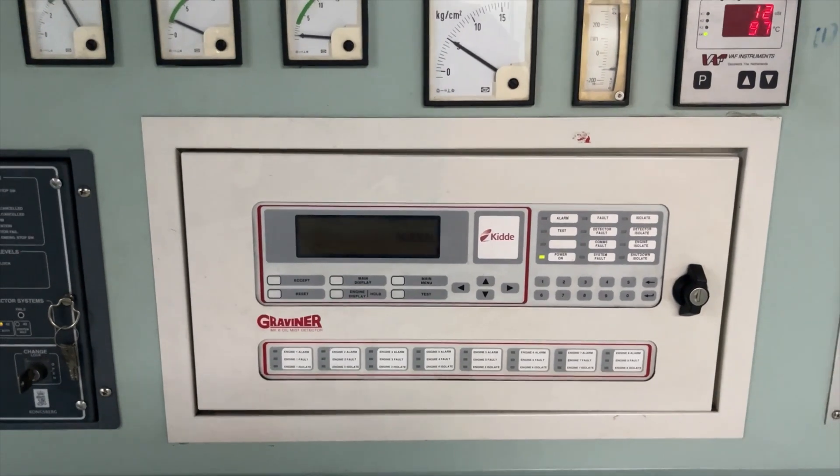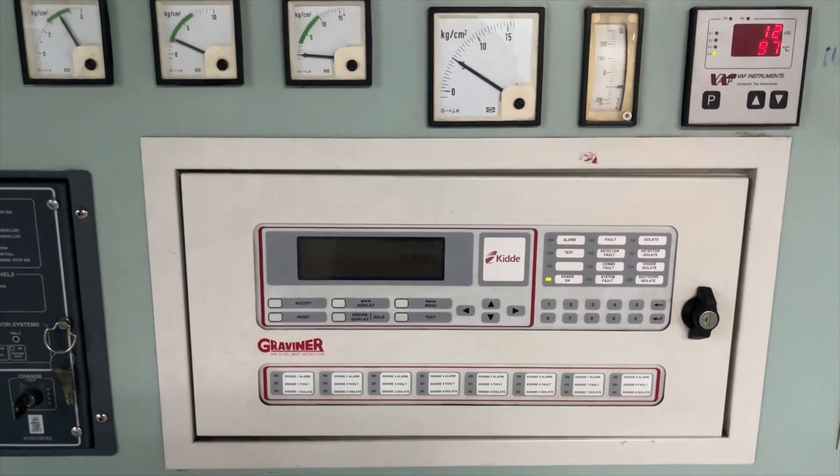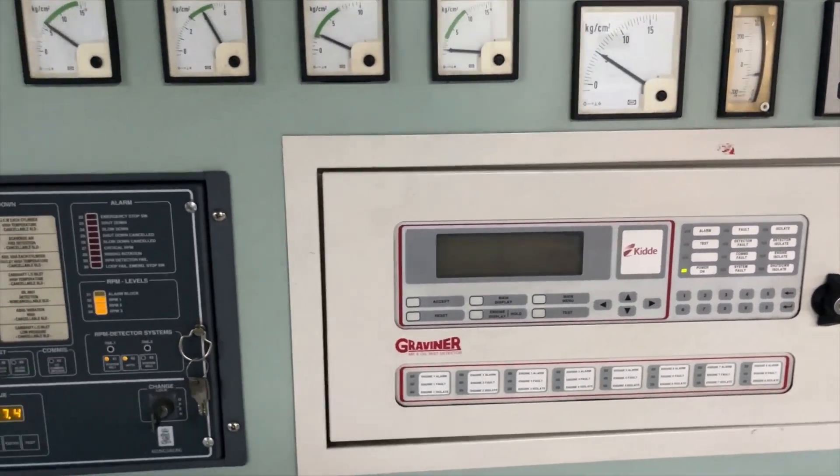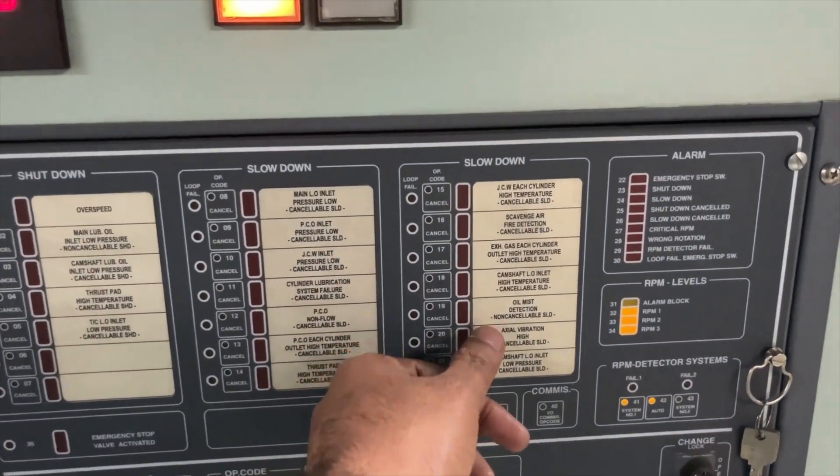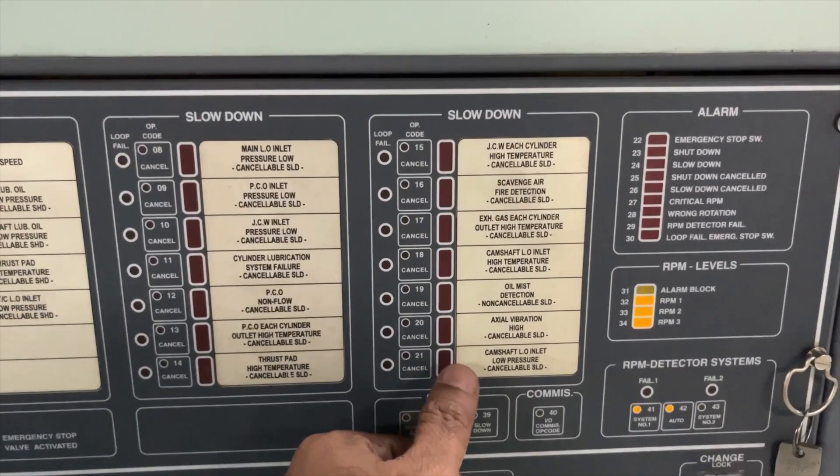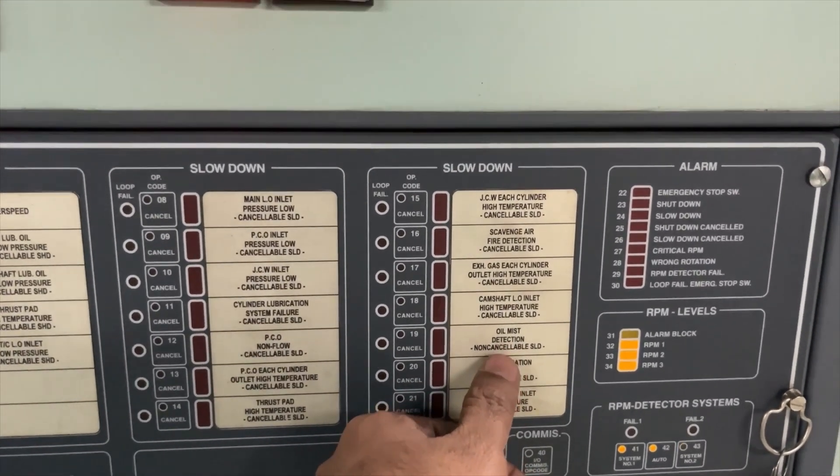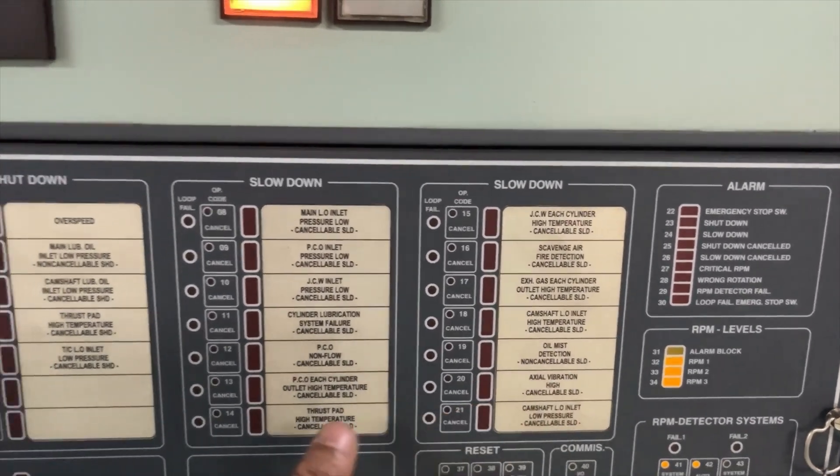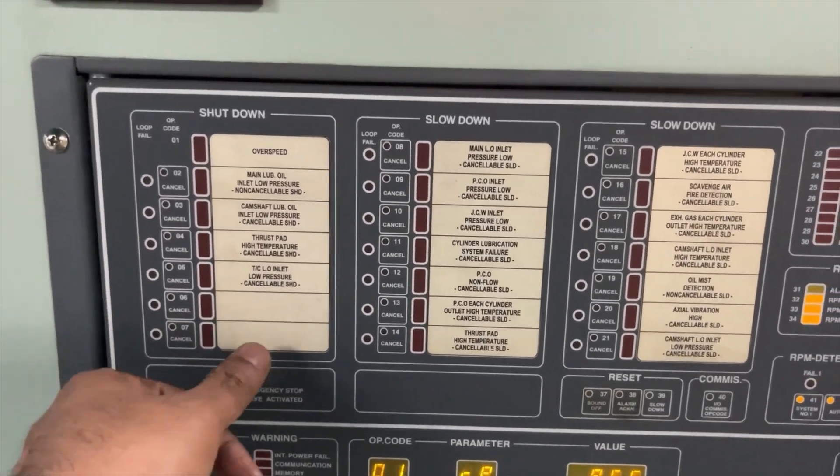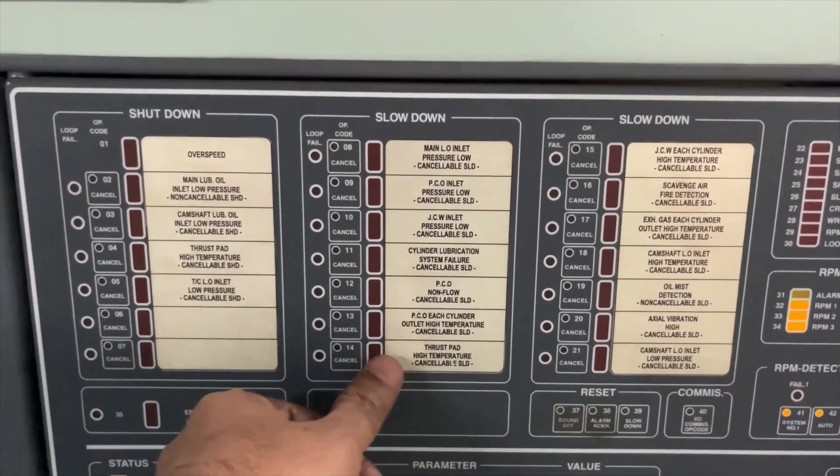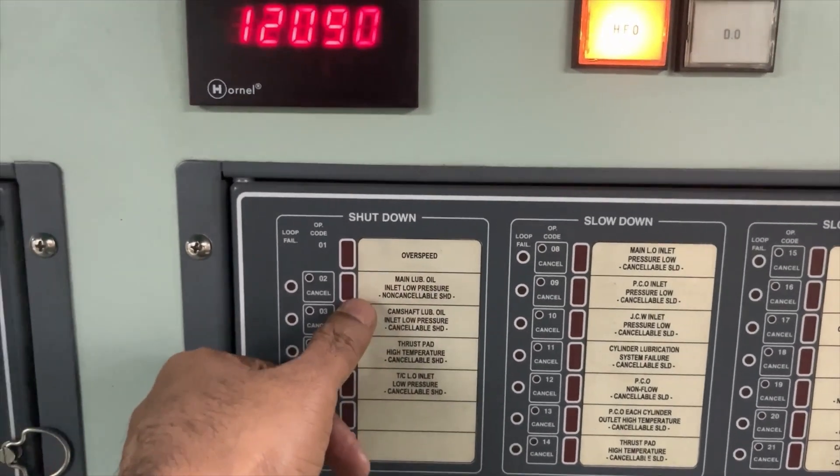This is for the protection of main engine. In case of crankcase fire, this unit is going to give the alarm and shut down. You can see here, this is a slow down, oil mist detection and non-cancellable. You will find few of the items which shut down, which are cancelable. All these are cancelable. This one is non-cancellable. These are cancelable.